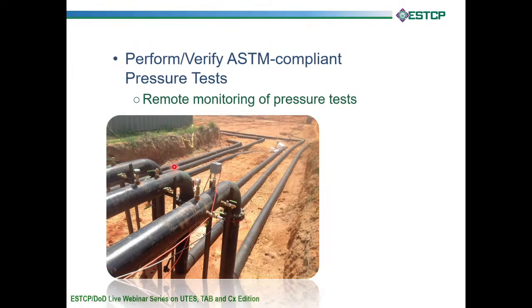We also like to perform and verify the ASTM compliant pressure test of the system. So this is the contractor pressure testing the whole system. And HDP is a little different than steel pipe. It stretches when heated, when out in the sun, and it actually stretches just when you apply pressure. So we wanted to make sure that there's a procedure for testing HDP. You want to make sure the procedure happened correctly. So what we did is we installed a pressure transducer here and a flow switch, just a flow switch like you'd have on your well at home if you're on a water well system for your drinking water.